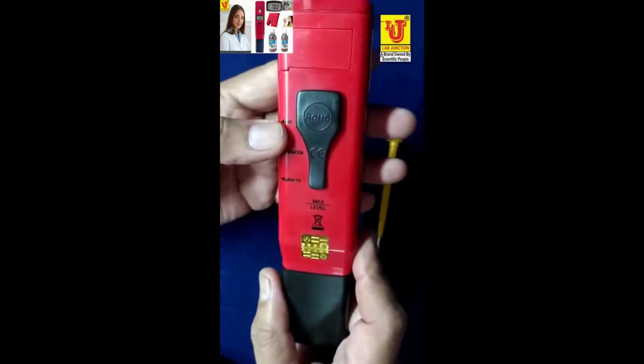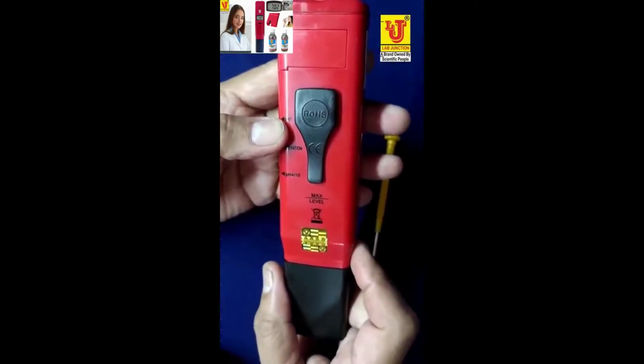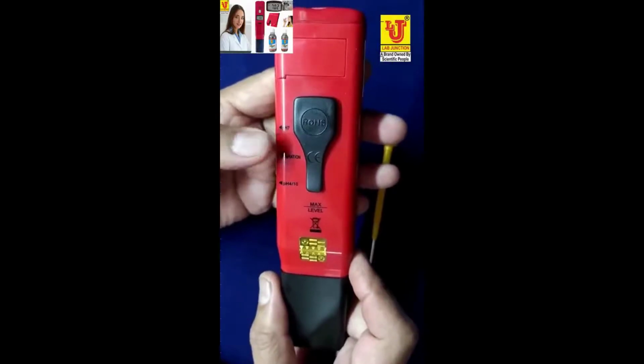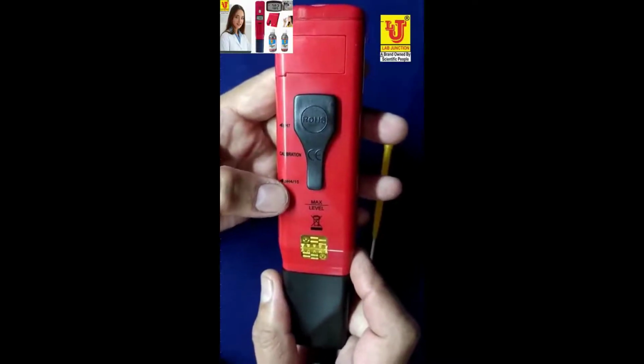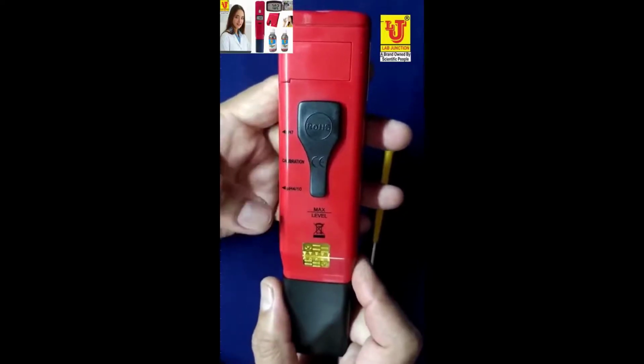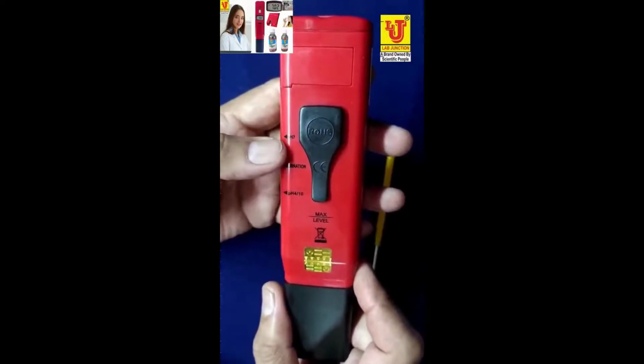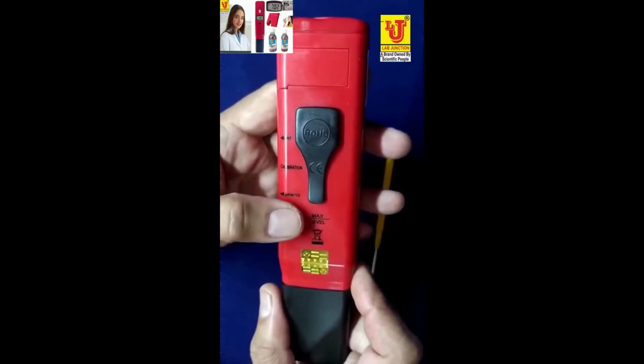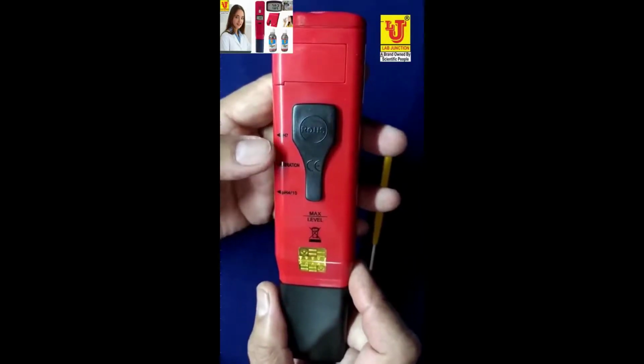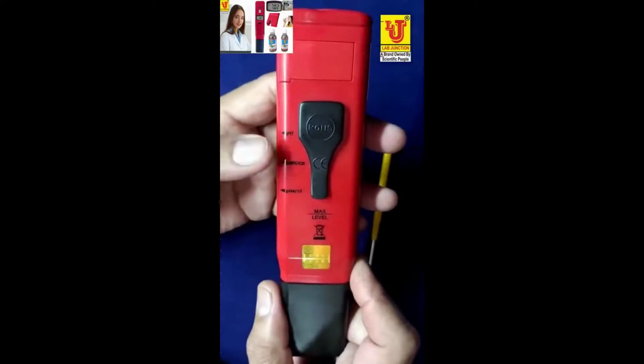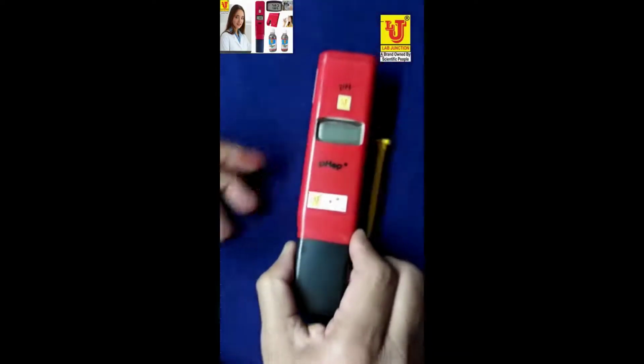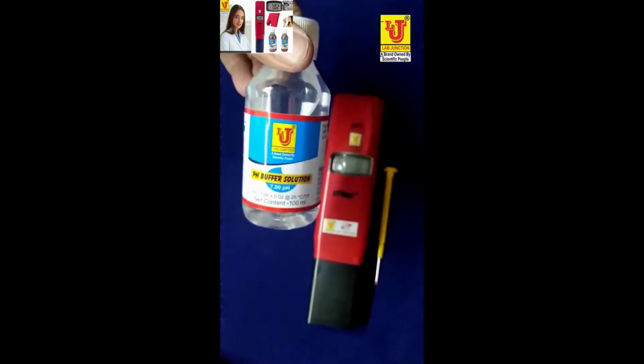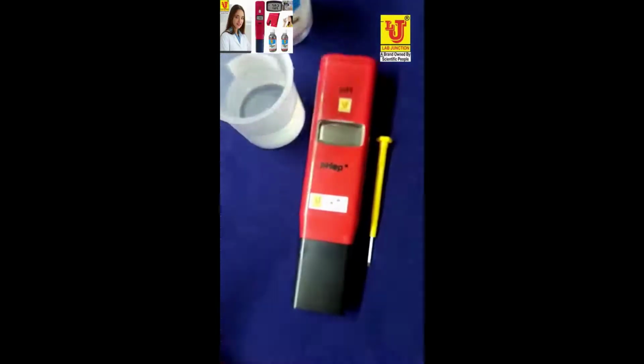You can calibrate only the pH 7 buffer. If you calibrate the pH 7 buffer, no need to calibrate the pH 4 buffer or pH 10 buffer. If you calibrate pH 4, no need to calibrate pH 7. If you calibrate the pH 10 buffer, no need to calibrate pH 7. Now I am calibrating only pH 7 like this. I am taking this pH buffer 7. This is my pH buffer 7.